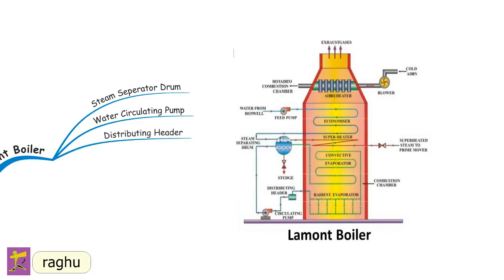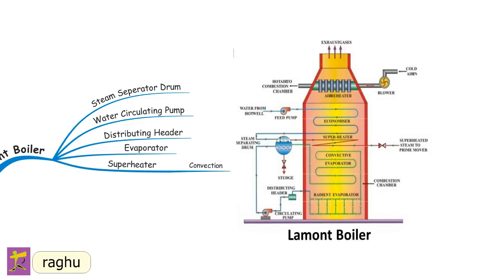The distributing header controls the flow of water to the evaporator tubes. The evaporator is used to evaporate water into steam. The convection superheater addresses the saturated condition of steam produced in the boiler — moisture in steam affects turbine blades and causes corrosion. To avoid this, the superheater is used to increase the temperature of steam and improve efficiency.